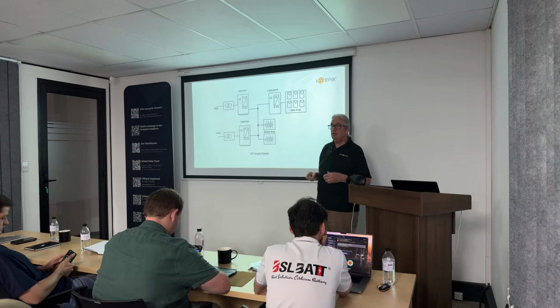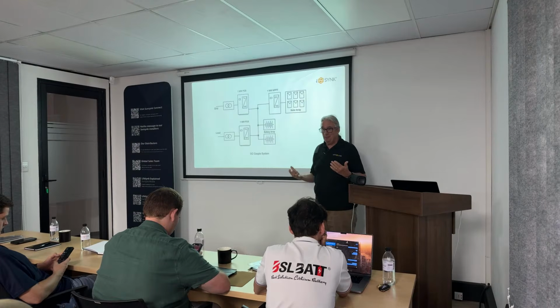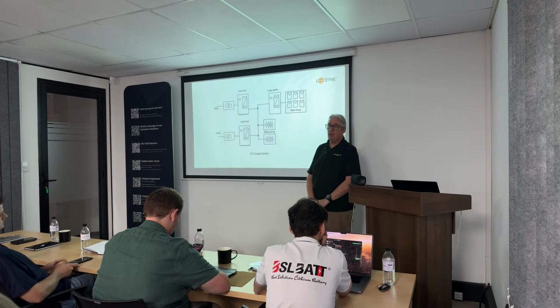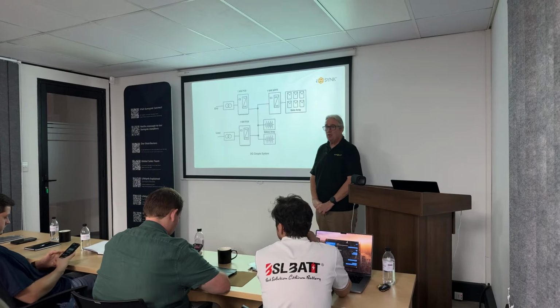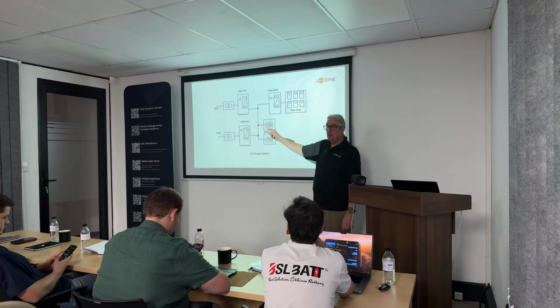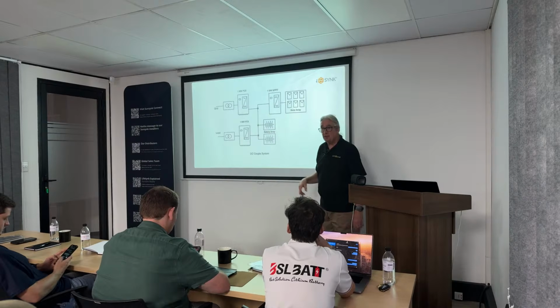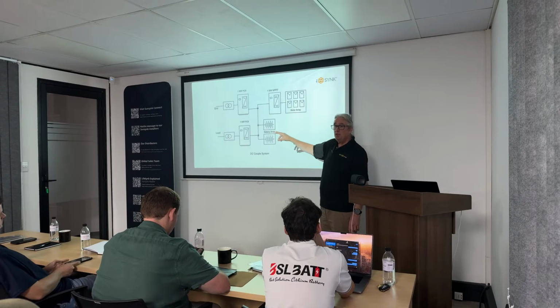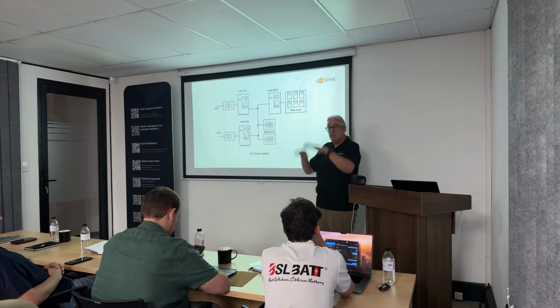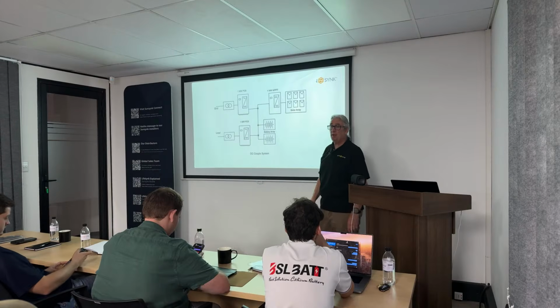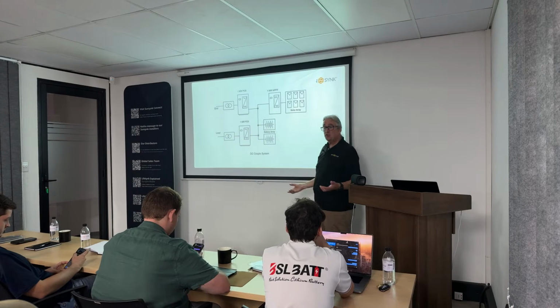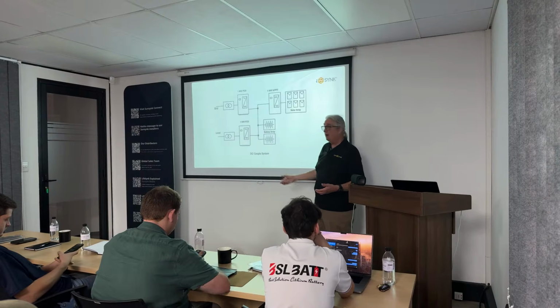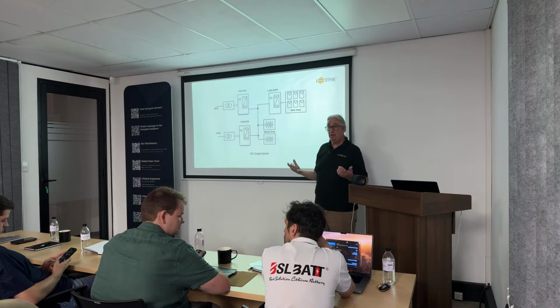But it depends on your grid, on what you're allowed. Often what they allow you in is what they allow you out, depending on the grid connection. If you've got a 500k connection, you can't put a 1 megawatt inverter on there because you'll damage switchgear and trip things. This is the nice thing about this system: if you only have 500 and want a 1 megawatt, you need a buffer, and this system can give you that buffer. Plus you're getting energy from the solar panels as well, so you might have a constant 1 meg out depending on your solar array, with a constant 500k coming in.